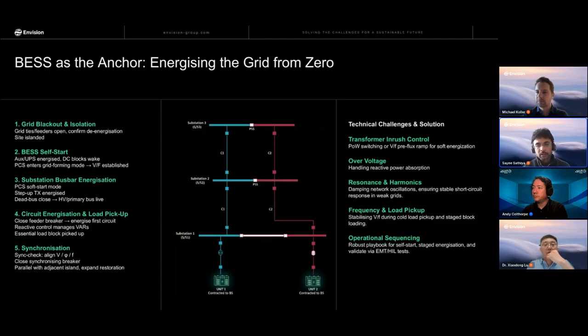And once we have energized the transmission system, basically we go into staged block loading. So the main thing we need to ensure is that we have sufficient energy in the batteries to provide the block load for the required duration. And there are certain minimum durations which need to be met by the BESS while participating in the restoration services. So these are some of the operation challenges that need to be resolved during the operation phase.